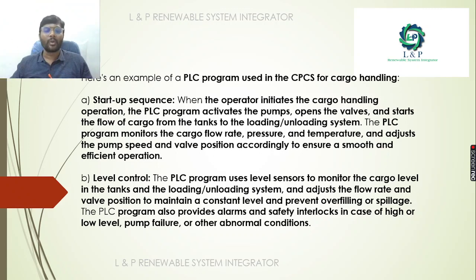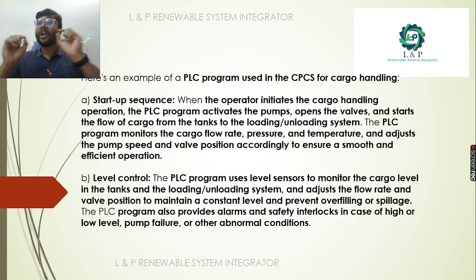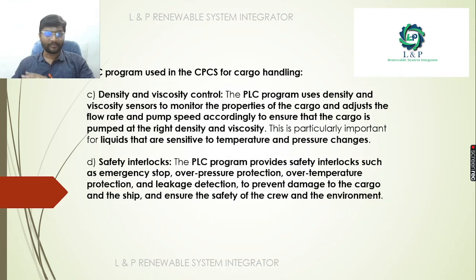Next is the level control. We have a program that uses level sensors to monitor the cargo level in the tank during loading and unloading, and adjusts the flow rate and valve position to maintain a constant level and prevent overfilling or spilling. We also provide safety alarms and safety interlocks in case of high or low level, pump failure and other abnormal conditions.